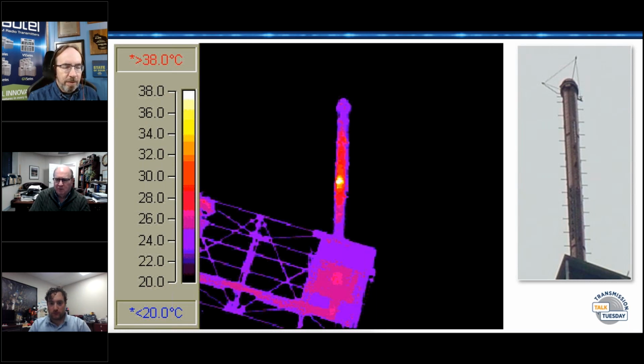A network analyzer uses a few milliwatts, so it won't see a lot of that stuff. You need to have something under load, operating. Same with power readings, when you're looking at power panels, make sure they're operating under normal load. If they're not, today everything looks fine, but next week you walk in and the phase looks hot because the air conditioner was running on that phase that day. So again, pay attention. It's not just the device, it's the things around the device.